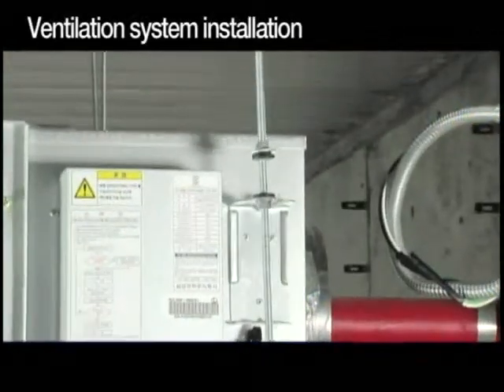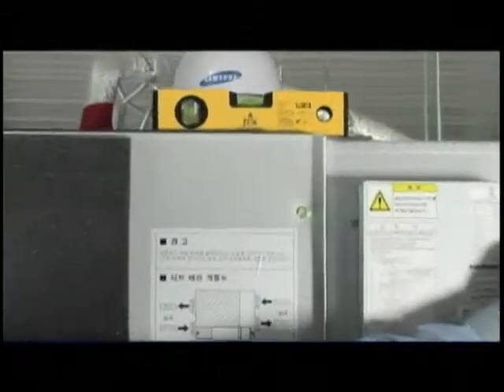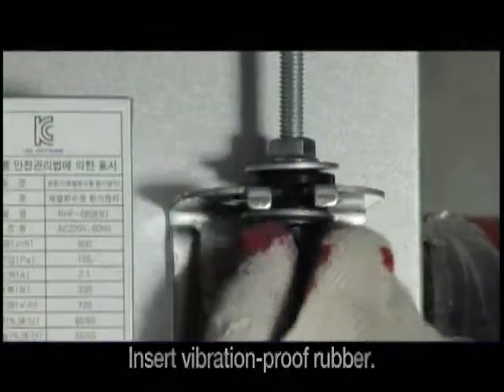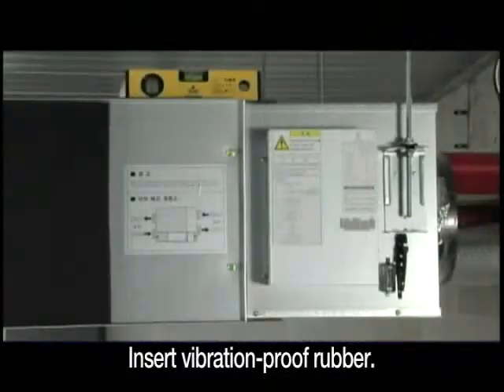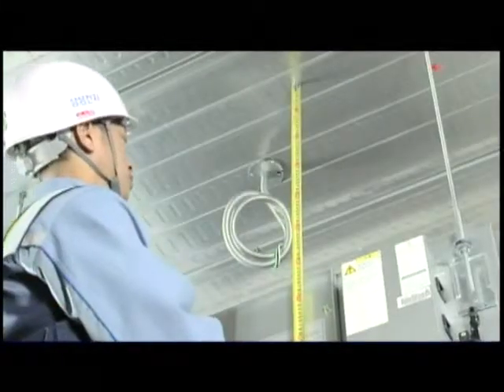When mounting a ventilator on the bolts, check the levelness by using a level meter, and to prevent vibration of the equipment, fill it up with vibration-proof rubbers. The space between the ventilator and the ceiling should be maintained 20 millimeters and over.